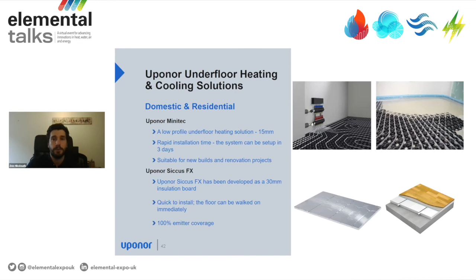Moving forward to more commercially used systems, which are used in residential applications too, we have the traditional in-screed system. The in-screed applications are the most common type of underfloor heating systems that are being used. There are many different ways that the pipes can be installed in the screed, and Uponor can offer all these types of systems. The most commonly used is the tacker system, where pipes are clipped on top of rigid insulation. It's a very easy to install system and very cost efficient. We can also offer the Nubos system, which is a castellated panel with a sticky lower surface, something like a big Minitec. It's an ideal solution when there is no insulation below the screeded floor. Both these systems are easy to install and have high performance for both heating and cooling.